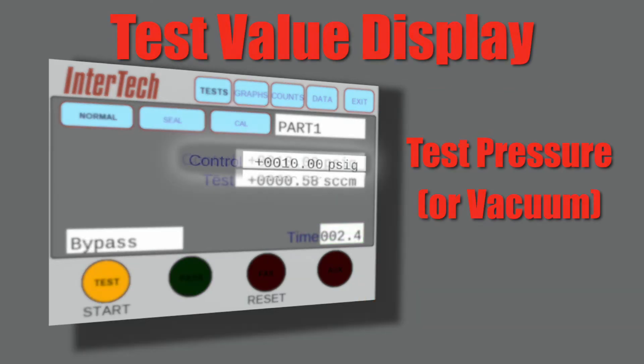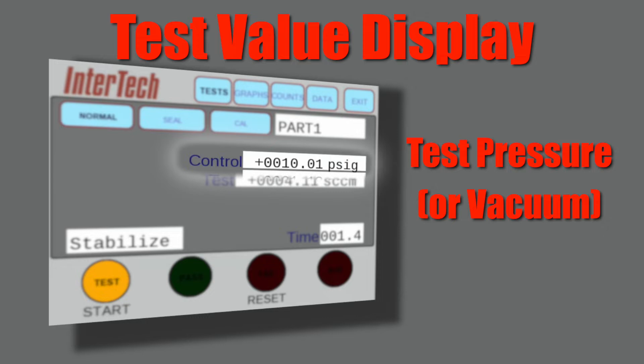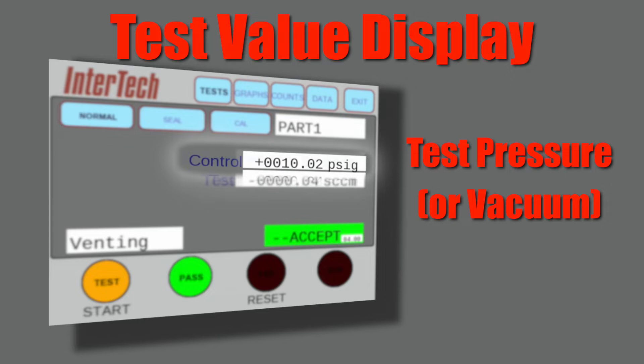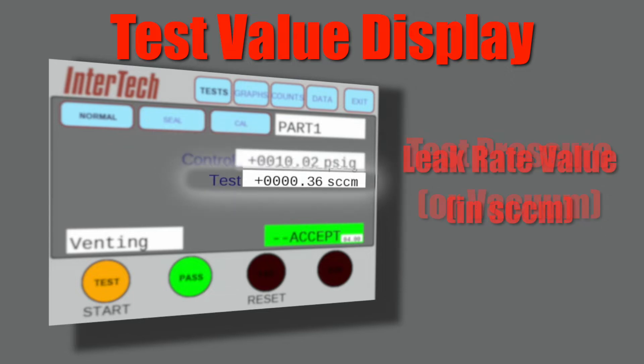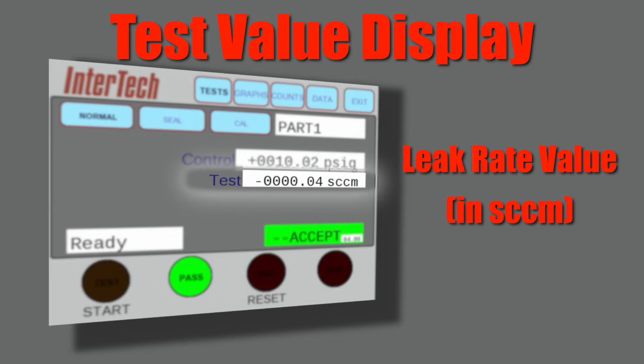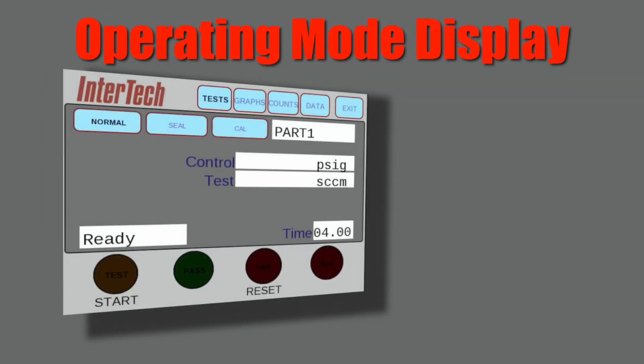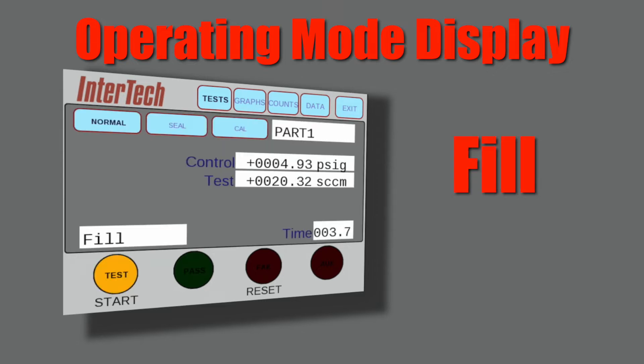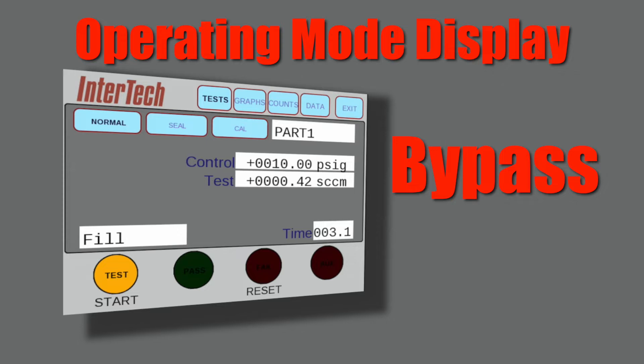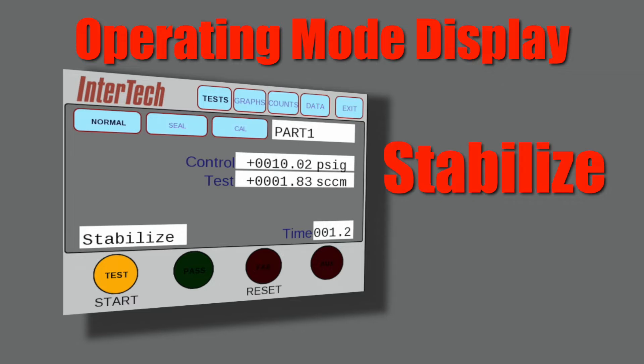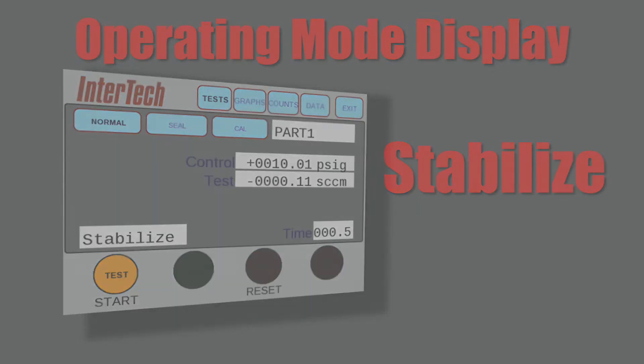The test cycle operation includes test values displays for test pressure available in selectable units and shown here in commonly used SCCM. The operating mode display shows ready when ready to start the test. The test starts with the fill cycle transitioning to bypass. The bypass mode is gross stabilization isolated from the mass flow sensor, followed by stabilize which displays the real-time leak rate flow as part stabilization happens.